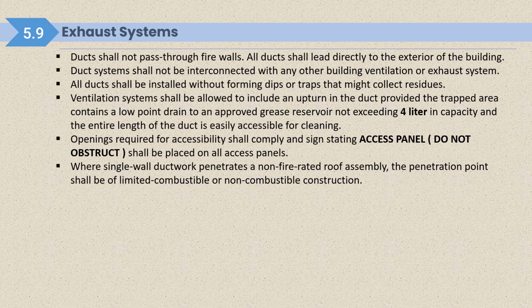All ducts shall be installed without forming dips or traps that might collect residues. So if there are such types of dips or traps that may collect grease residue, we should avoid that. The ventilation system shall be allowed to include an upturn in the duct, provided that the trapped area contains a low point drain to an approved grease reservoir not less than 4 liter. That is the same provision that we talked about near the grease filter. Beneath the grease filter, we need to provide one container of not less than 4 liter.